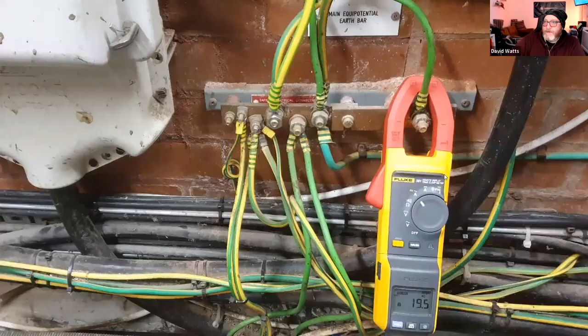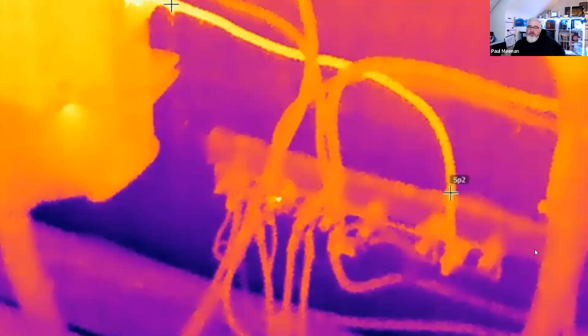Moving on, again back to this image - I think we've used this in previous webinars where you've got 19.5 amps flowing through an earthing conductor. And then if we put a thermal image on it - Mr Watts, you are our expert. Yeah, as you can see, you've got the connection here of SP2. The point of this earthing conductor is smaller than the majority of other earthing conductors, and in that case it shows more clearly that there is energy on this earthing.